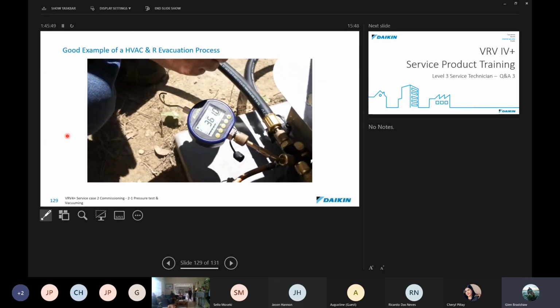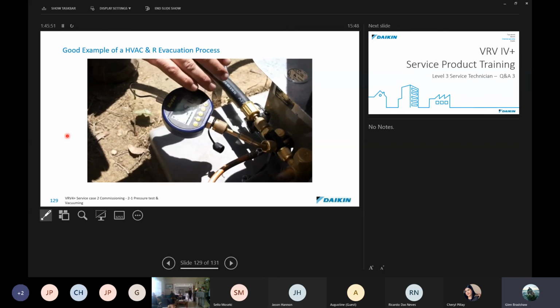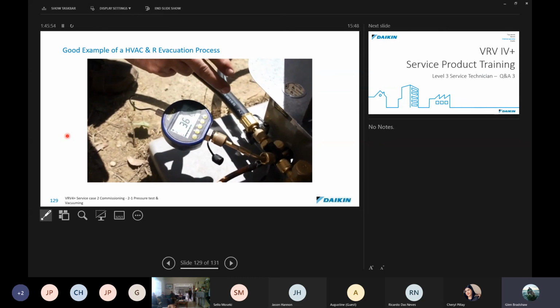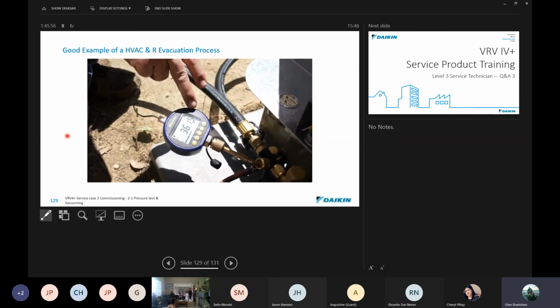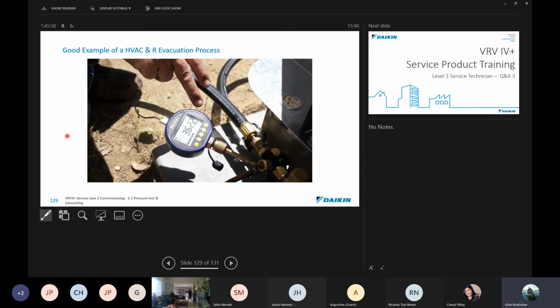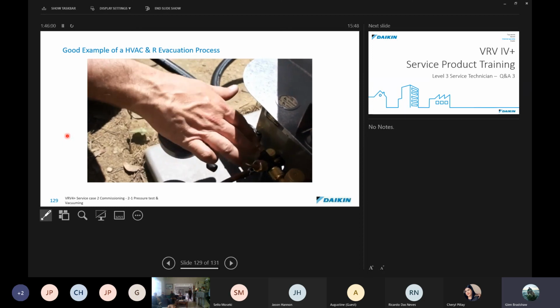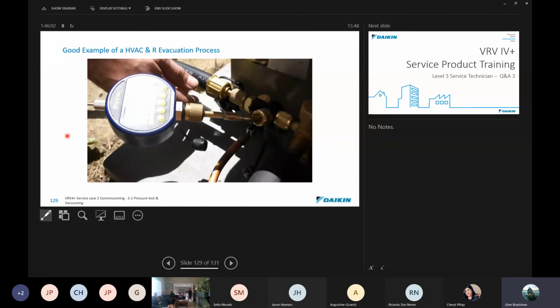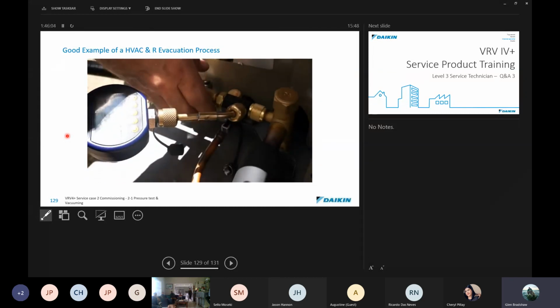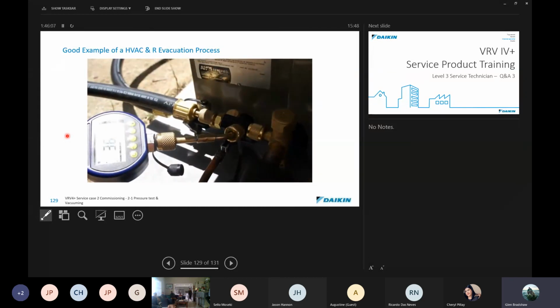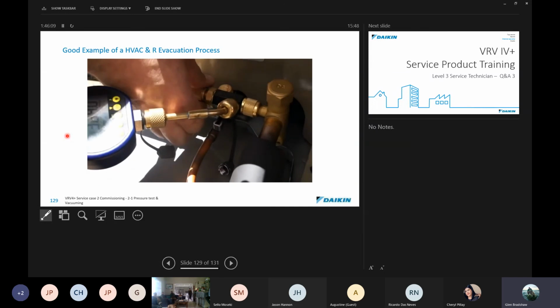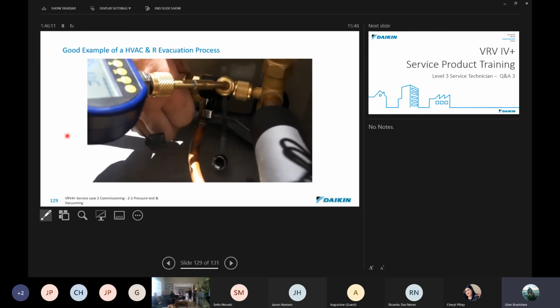Now I've got the core tools isolated right now, and I don't want to take my micron gauge off yet, because I don't want to introduce air into the system. If I pull the micron gauge off, we're going to pull air right to the side of the core tool here. So I've got these two closed. I'm going to go ahead and shut off my pump, and we'll disconnect our two hoses here.